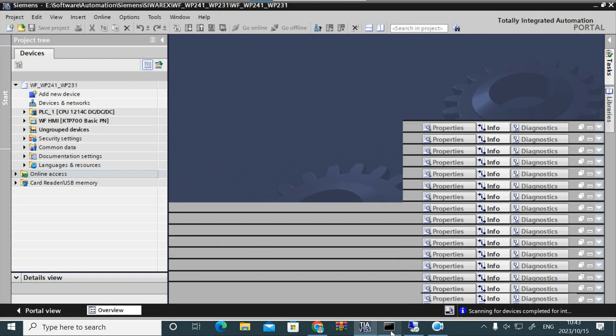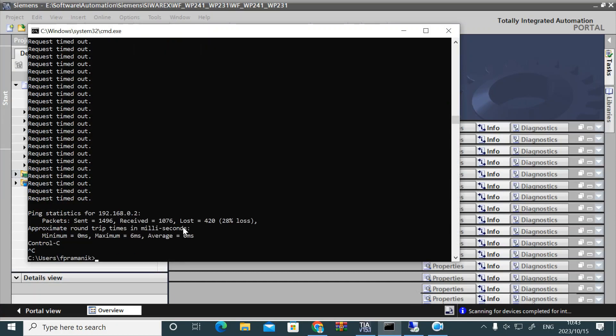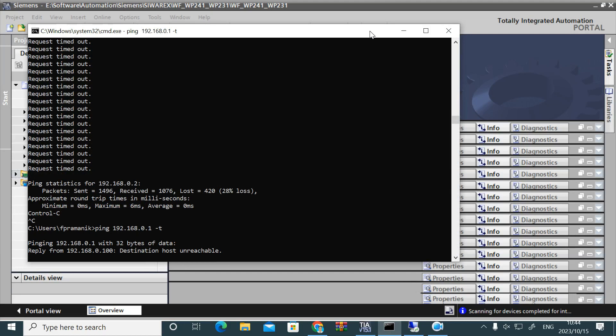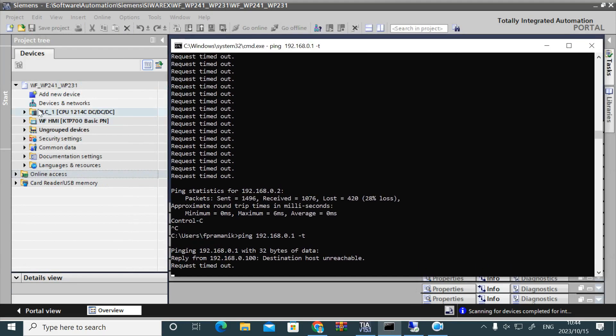For those modules, you have to set the IP address another way — you can set it by TIA Portal. Let's see how. I have connected a new PLC to my laptop and I want to ping the IP address 192.168.0.1, because some PLCs come from the factory with that IP address set. As you can see, it is not pinging, which means it has no IP address set.